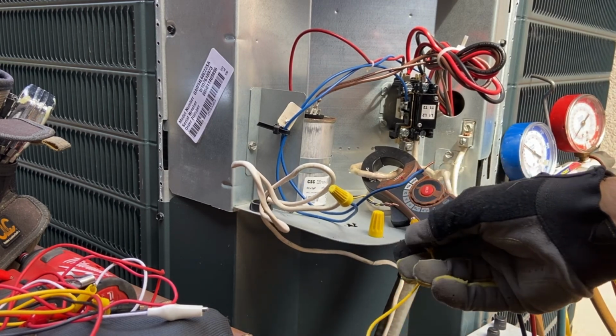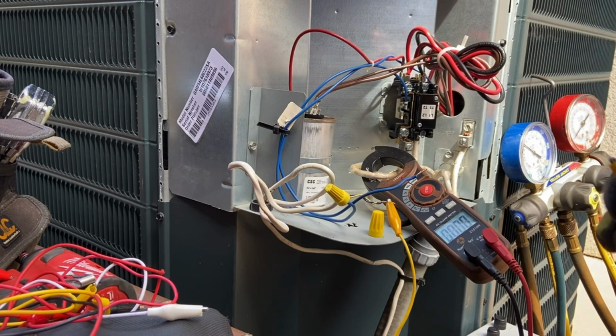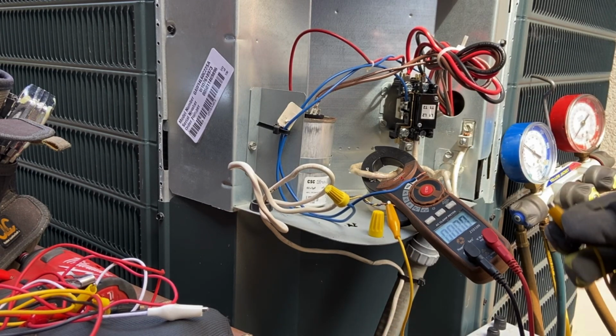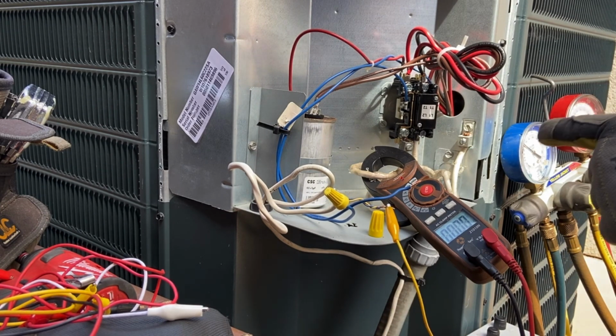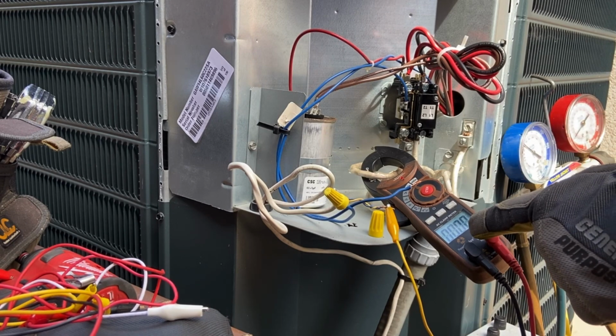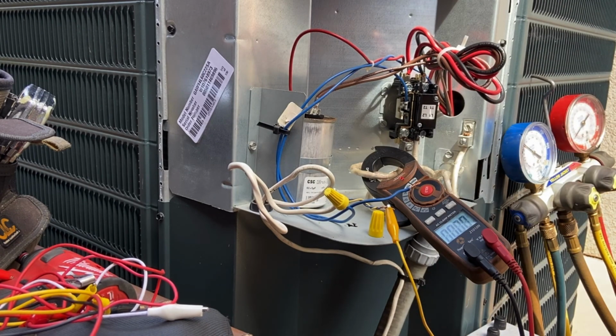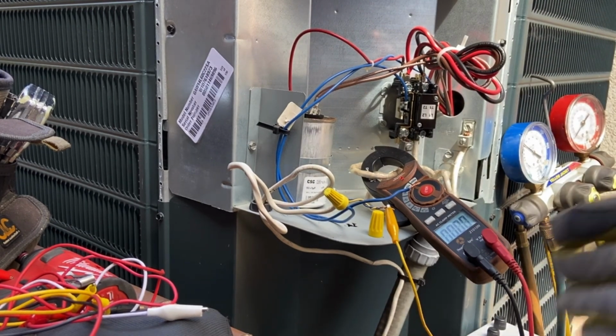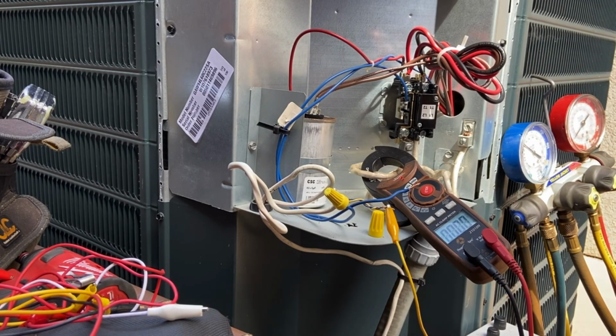Put it on one side of the wire, and when I connect back to my other side of the wire, the unit's going to start. I'm going to watch my refrigerant gauges over here. I'm going to watch my amperage on startup, and all this tells me if everything's running okay. I know, looking at my nameplate on my unit, my total amperage on the hottest, most difficult day for this unit is going to be about 28 amps. So I'm expecting something less than 28 amps. If I get something closer to 50, I know I'm about to blow my fuses and I want to shut it off and start checking out what's going on. So let's start it up.